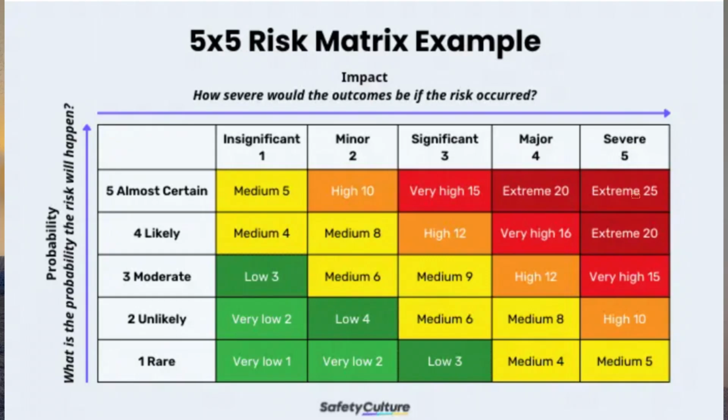What I mean is, if one of the risks could lead to catastrophic harm to your patient, and you have reduced the risk, now you have to revisit and evaluate that risk to see if the new risk is acceptable or not, because you can never eliminate it, right?